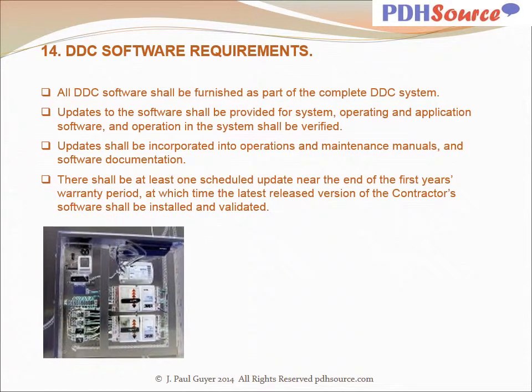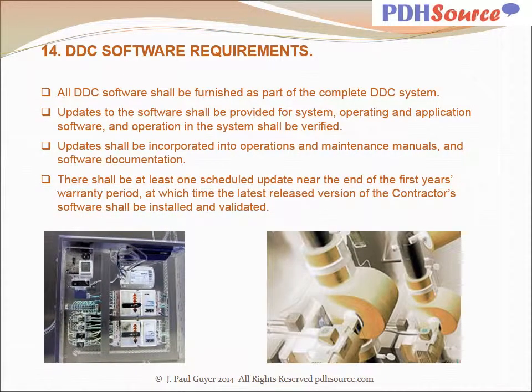All DDC software shall be furnished as part of the complete DDC system. Updates to the software shall be provided for system operating and applications software, and operation in the system shall be verified. Updates shall be incorporated into operations and maintenance manuals and software documentation. There shall be at least one scheduled update near the end of the first year's warranty period, at which time the latest released version of the contractor's software shall be installed and validated.